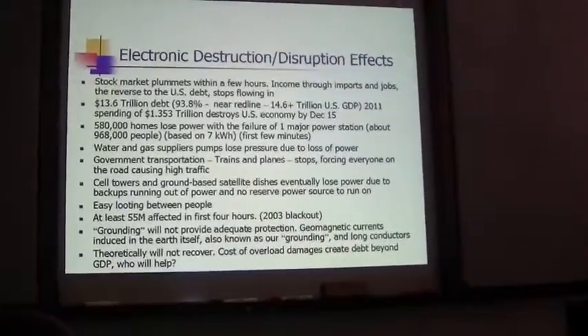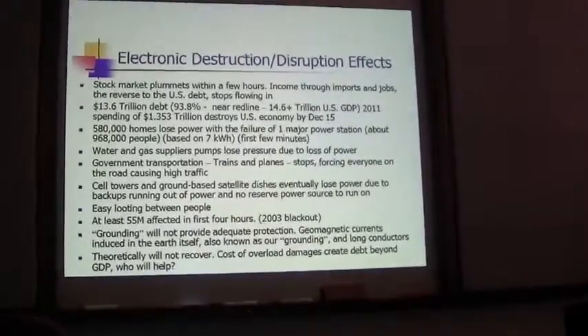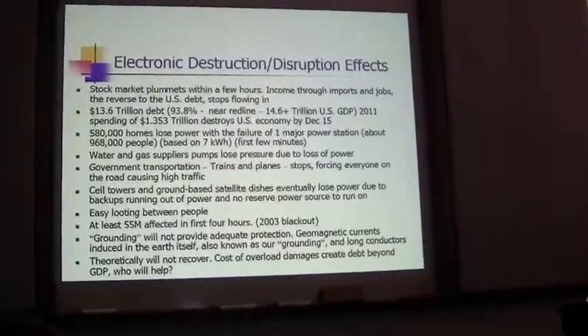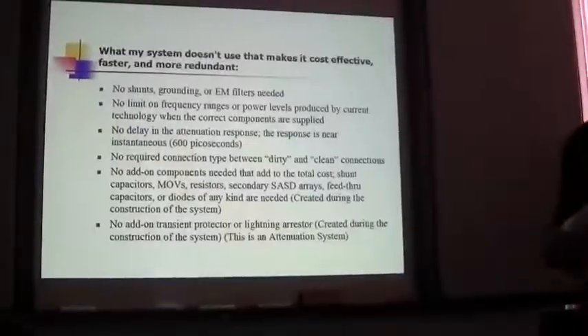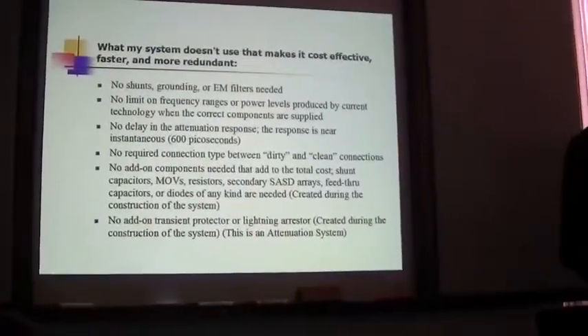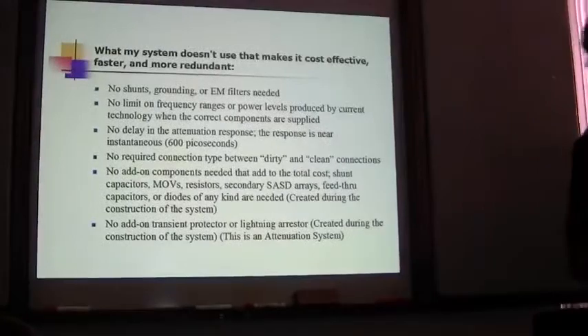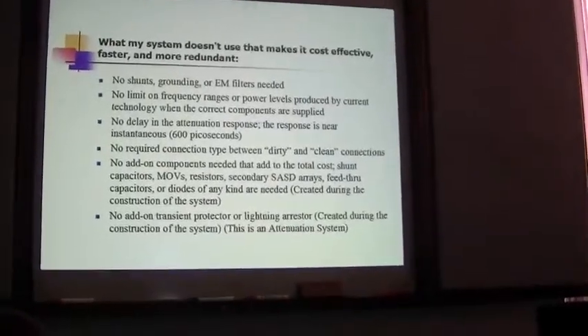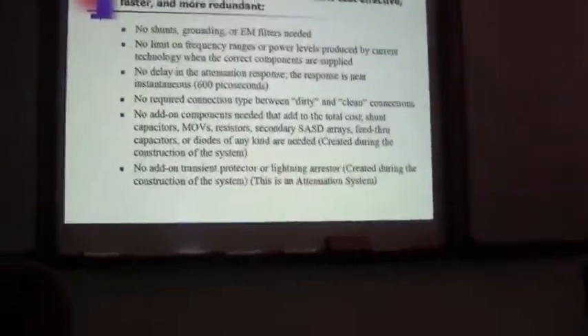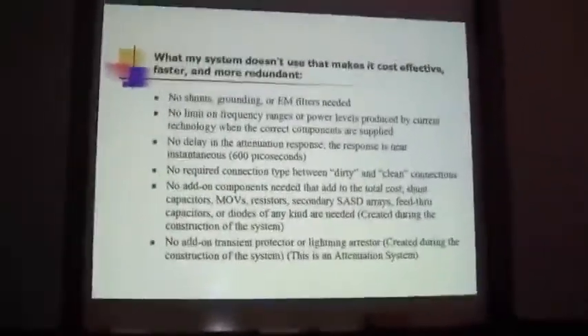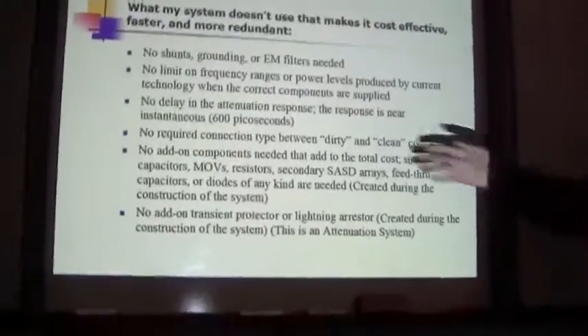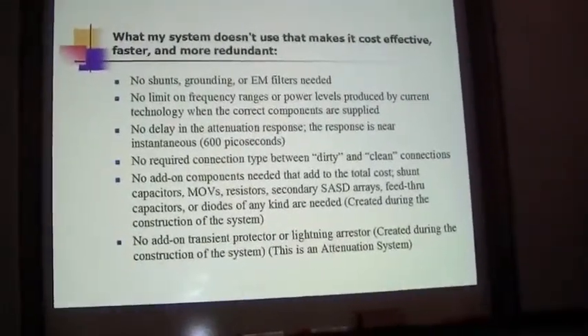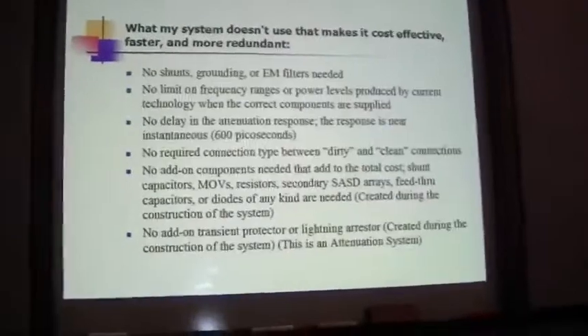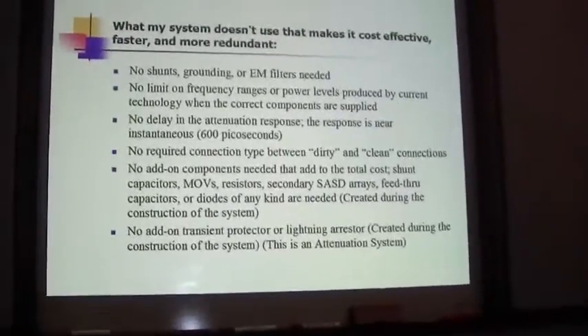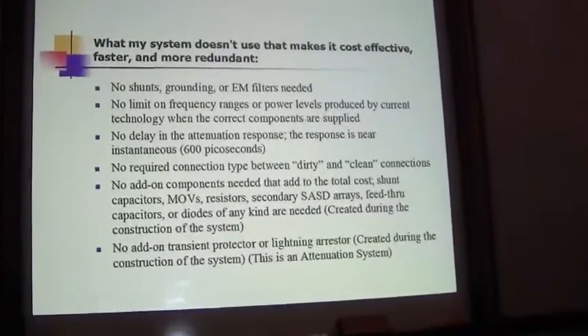My plan will only take 1.5 years to implement, based on an 8 to 10 hour building cycle. There is no measurable delay in attenuation response. It's around 600 picoseconds, and that gives the system the chance to attenuate the current flow before it leaves the actual attenuation system. There are no required connection types between so-called dirty and clean connections. A dirty connection is where the surge will come in. A clean connection is the modified, attenuated surge.